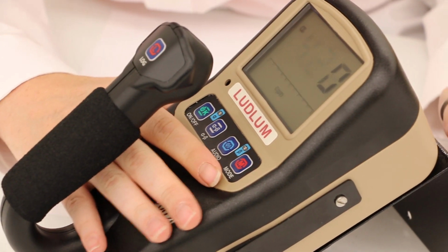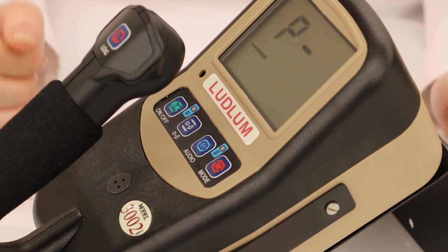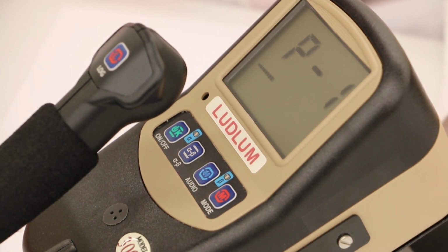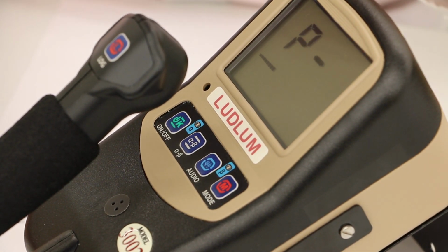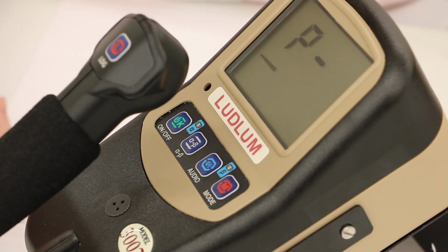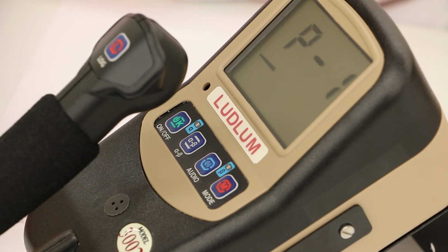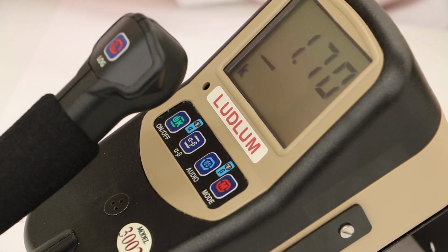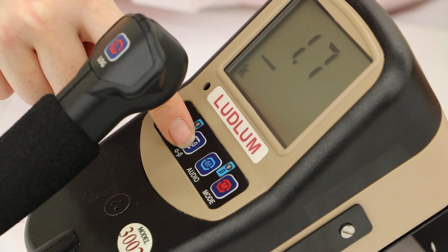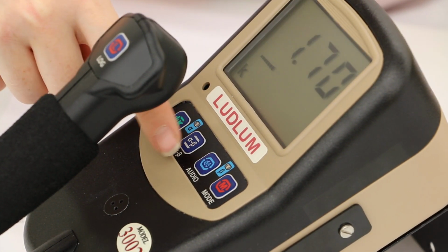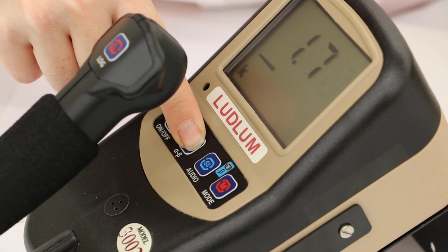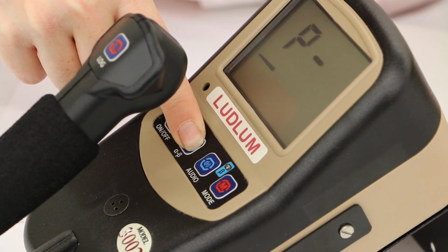Once it is, you only have a 4-second window to press the mode button 3 times to access the device menu. Once inside the menu, you will have page 1, which contains the calibration specific stuff for this, like the high voltage, the response time, overload setting. In there, to access it, you'll press the alpha beta button, and the first thing you see is the high voltage set point. Holding the alpha beta button for about 3 seconds will return you to the page selection menu.